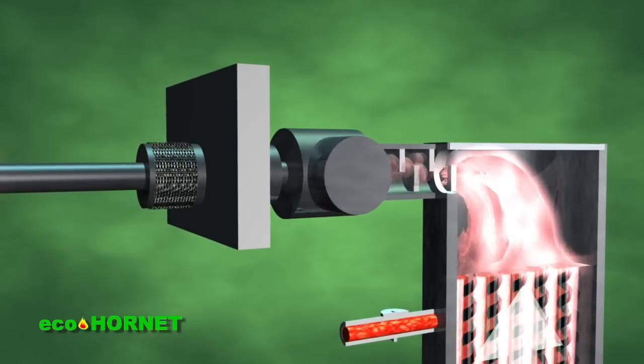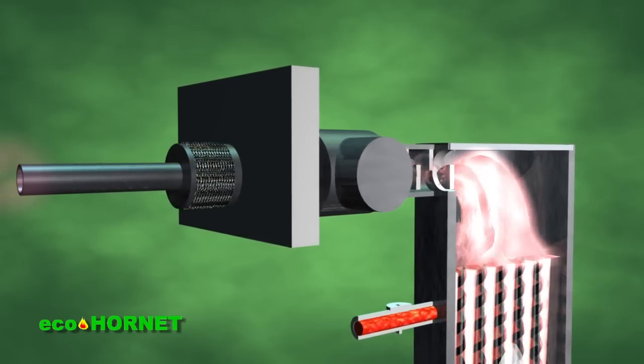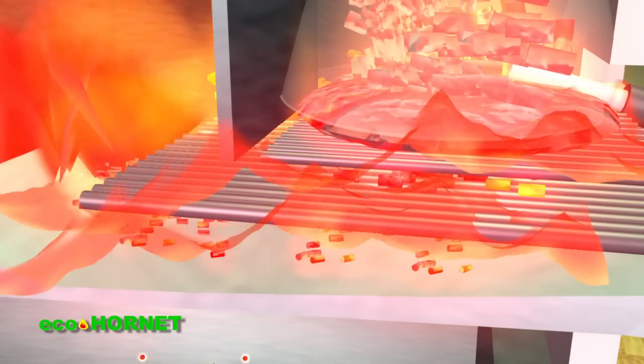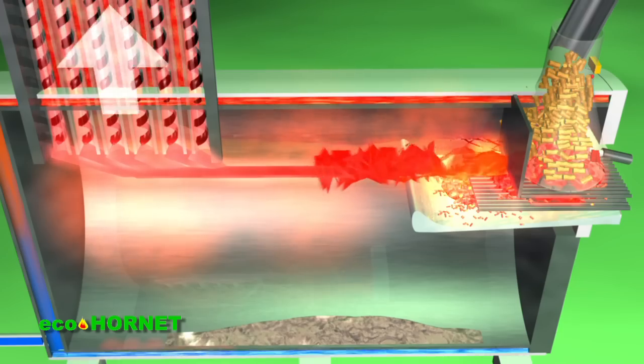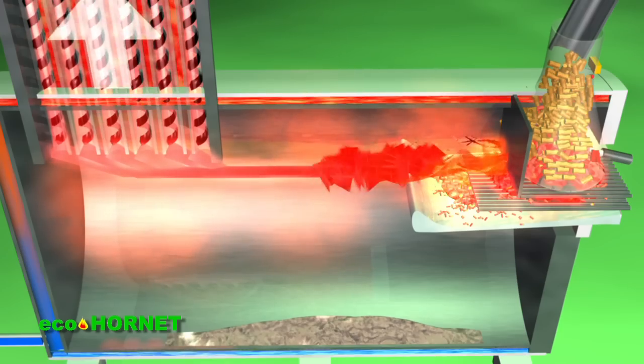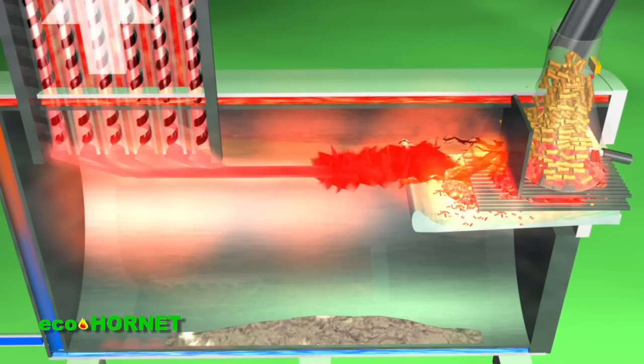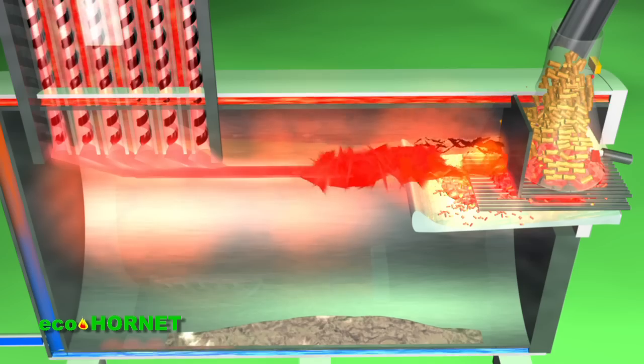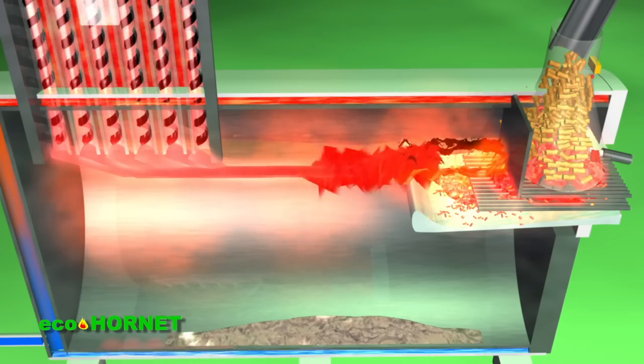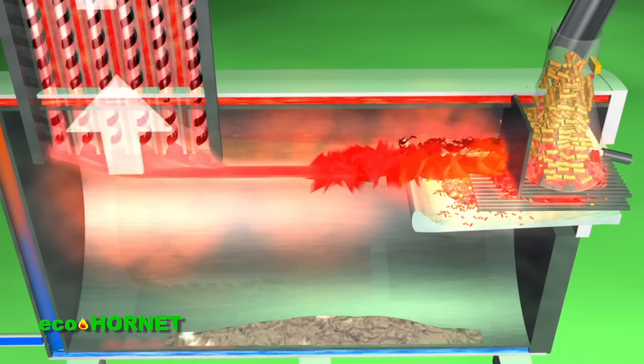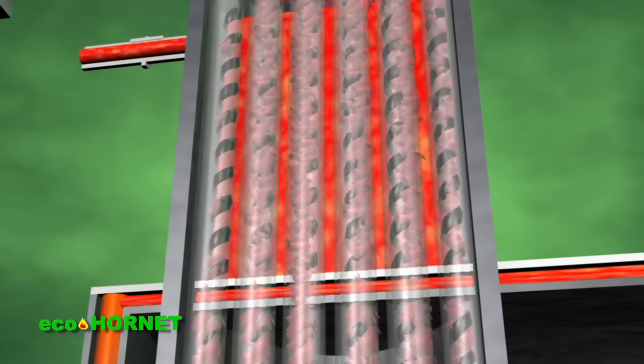The smokeless combustion without creosote deposits is possible due to an adequate distribution and dosing of combustion air and of secondary air. The building model of the gravitational burner, as well as the distribution pattern of the combustion air, ensure the combustion of the fuel and of the ash and creosote particles of the combustion gases. The automation ensures a constant air volume and combustion dynamics in order to achieve a complete combustion of fuel and high efficiency.